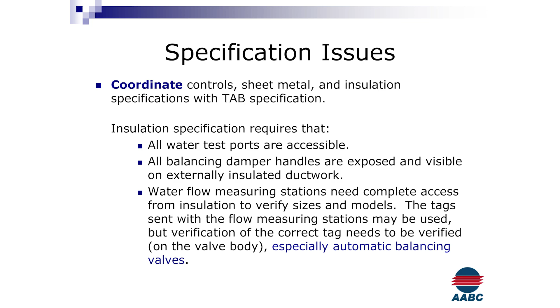Water flow measuring stations need to be complete, accessible, or need complete access from insulation to verify sizes and models. One of the things that they try to do is they'll cover up the valve, but they'll leave the handle exposed so you can just see the handle. Well, that doesn't help me because I still have to cut out the ports. So beyond not being able to see, to verify sizes and model tags, the tags sent with the flow measuring stations may need to be used for verification.